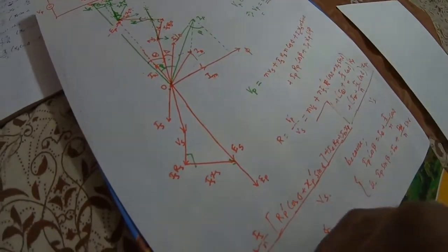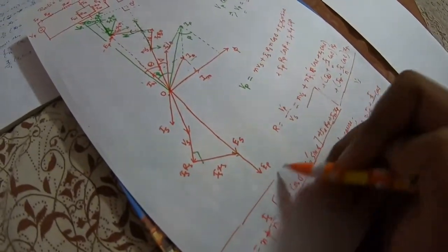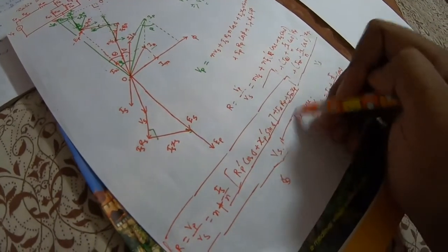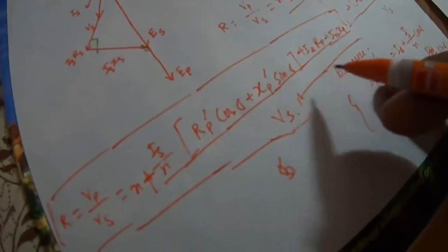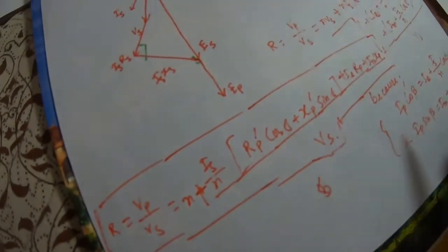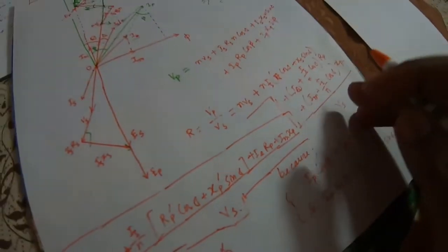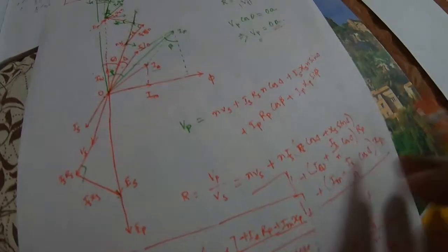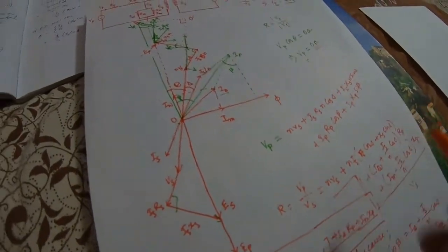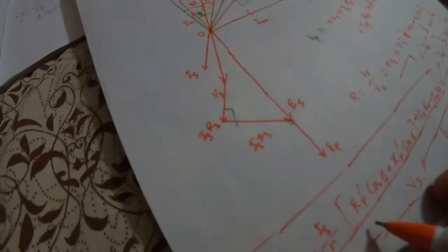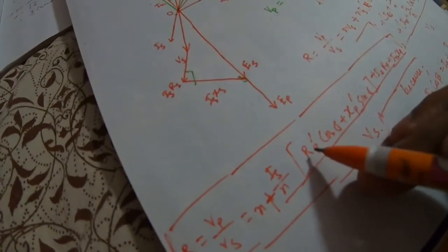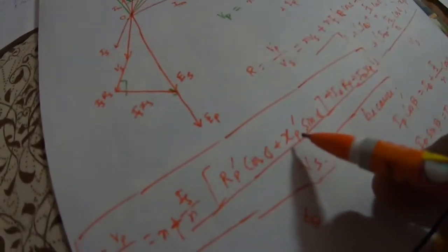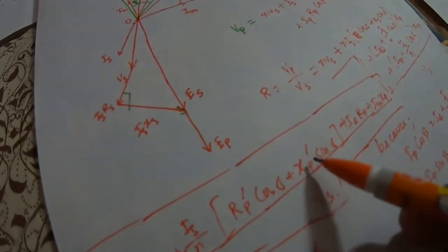So now what is over there? So now this is actually the final formula. So this is the final formula of your ratio error for a PT. So now the question is that, so why we are having this Rp dash? So after calculating and after computing so many values, this particular equation, we will be having a certain factor which will consider the equivalent resistance of the transformer referred to the primary side. So this Rp dash is nothing but the equivalent resistance of the transformer referred to the primary side. Similarly, this Xp dash is the equivalent reactance of the transformer referred to the primary side.